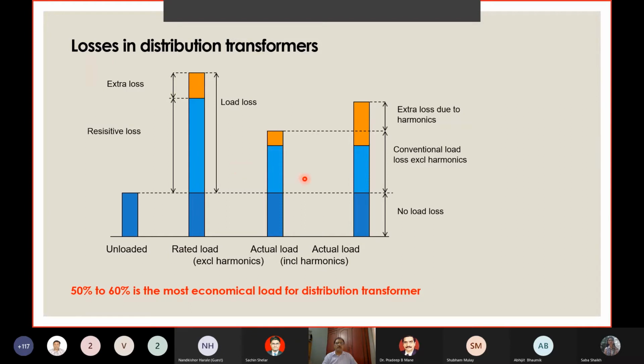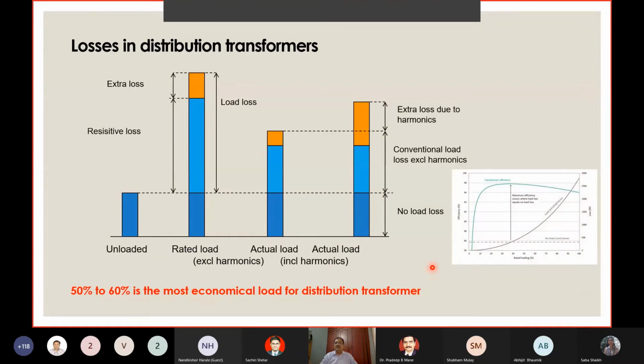So the ideal choice for a transformer is to limit the operations or loading to 50 to 60%. It is the most economical load because most of these transformers have an efficiency curve like this. Their best efficiency happens, oil-cooled transformers particularly, around 40%. So beyond 40%, the efficiency keeps dropping. At 100%, you will see the lowest efficiency occurs. So you have to optimally load the transformer. The economic load factor is between 50 to 60%, where the drop in efficiency is not substantial.